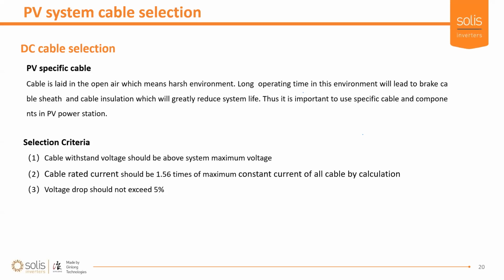Next, you need to make sure that the cable can actually handle the current. This is really, really important, the most important. You don't want melting cables, obviously. However, generally the voltage drop, the next point, comes into a problem before the current handling capacity.